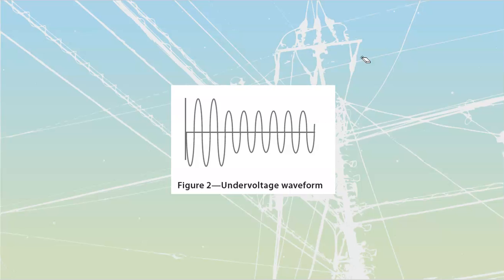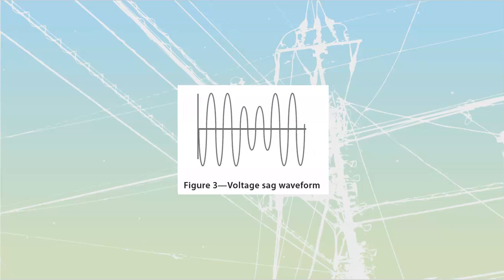Sometimes it can be these other ones that they talk about, loose or corroded connections, or inside of your own facility, unbalanced phase loading, where somebody decided they were going to take all the heaters in the entire plant off of phase 1 or something like that. Sag is not going to be complete interruption of power. In other words, it does not go all the way down to a value of 0. It is just going to go down to a low value, right?